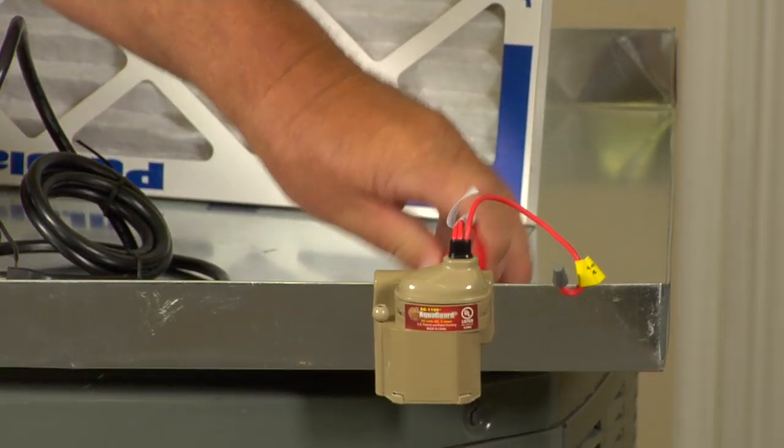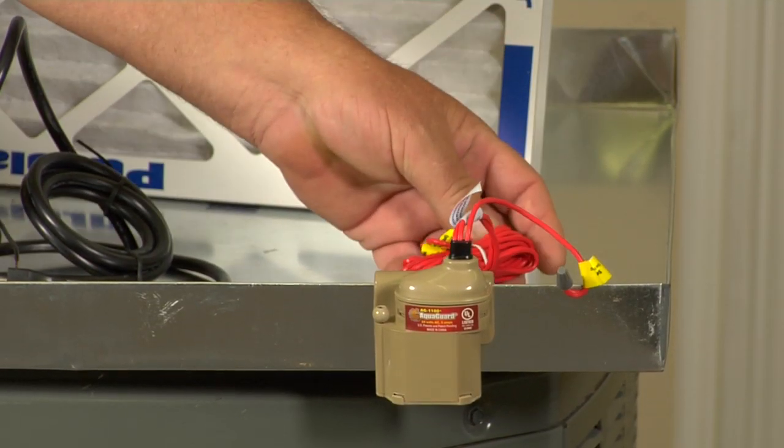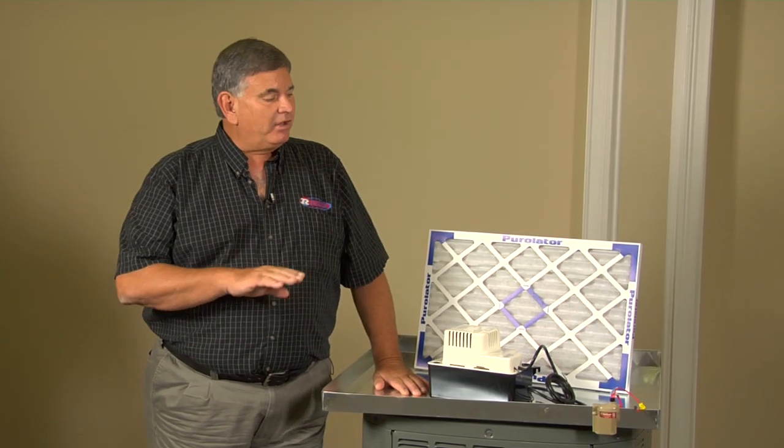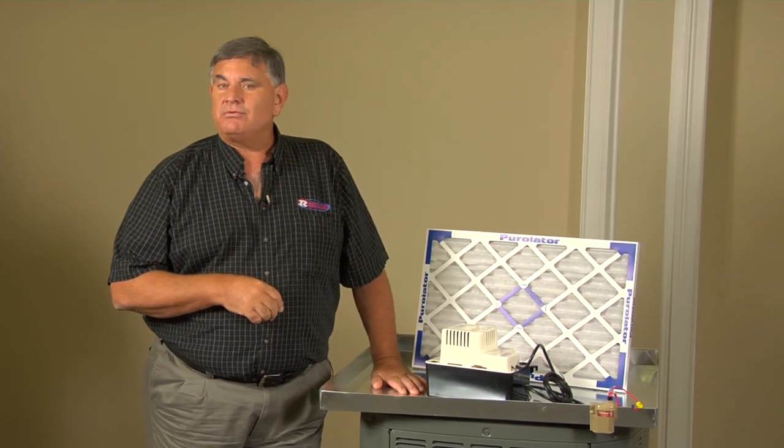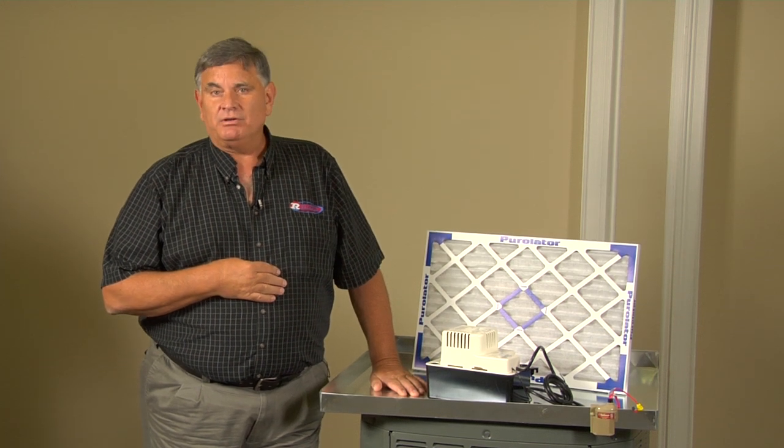Many times you'll have a switch similar to this in your drain pan. There's a little float mechanism on that. Make sure that that float is in fact all the way down and not accidentally lodged up. That will keep you from cooling.